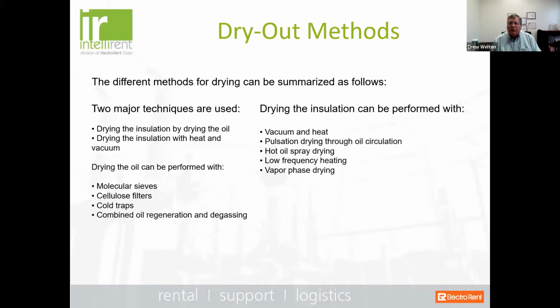Okay, so what if you determine you have a moisture problem? Well, there's a number of things that you can do, and there are different methods for drying that are summarized in two different ways. Drying the insulation by drying the oil, which is typically what we've seen in North America, or drying the insulation by putting it in a vapor phase chamber. But this certainly isn't something that's practical for aged transformers. Basically, if you were going to put it in a vapor phase chamber, you'd have to detank it, send it back to the factory, and then do your vapor phase process there.